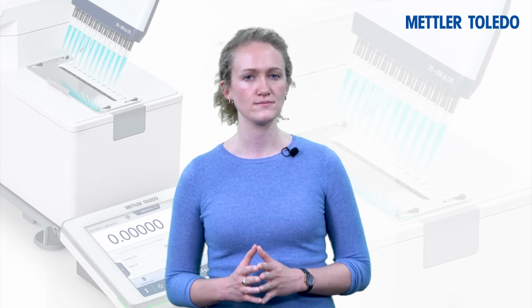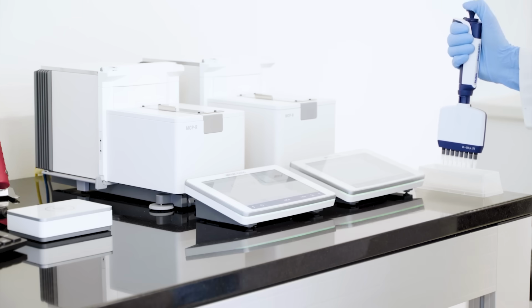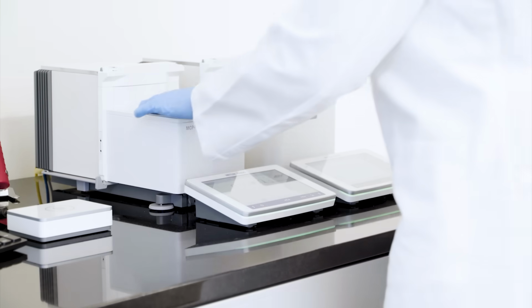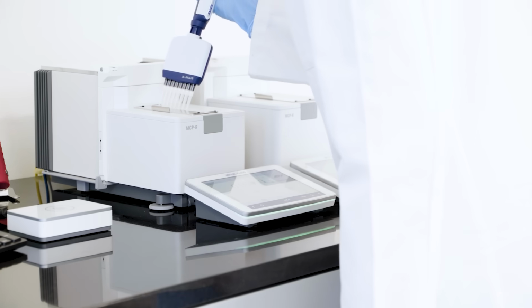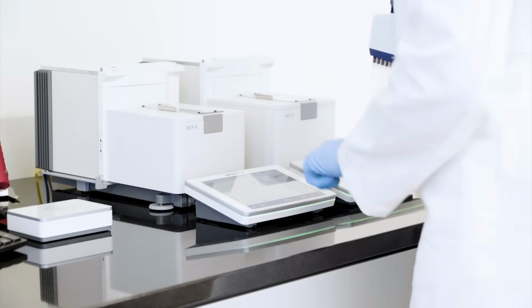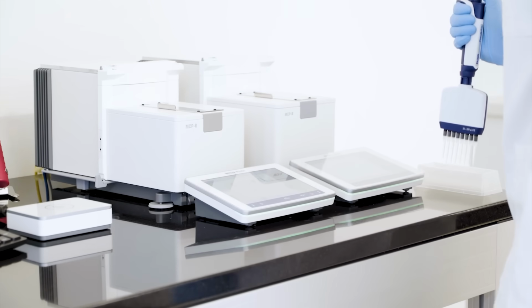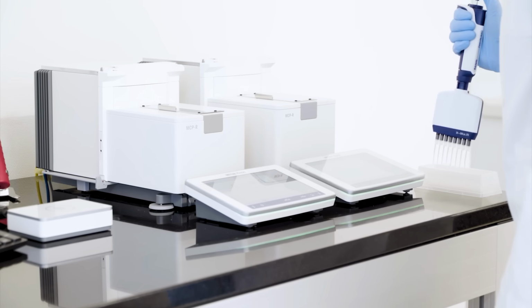Additionally, two MCPs can be connected for increased productivity, enabling you to complete two simultaneous measurements. With this configuration, it takes as little as 15 minutes to complete the 30 dispenses required for a full calibration.